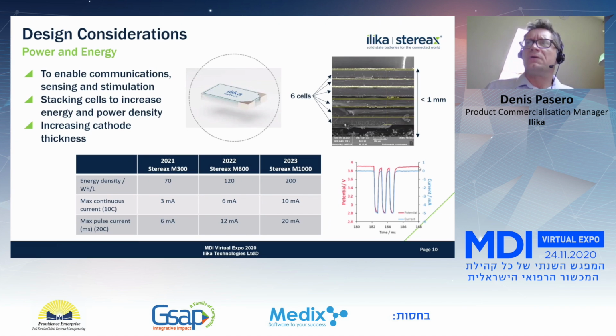The second consideration you will likely have is, how can such a small battery provide enough energy and power for my device, for enabling communications or sensing or stimulation? What we do is, again, stack those cells on top of each other. You have a little cross-section photograph on the top right here of 6 cells connected to each other in parallel to increase capacity, and you can see it is still less than 1 millimeter thick. We also increase the cathode thickness, which is the lithium reservoir, in order to provide enough current for pulses.